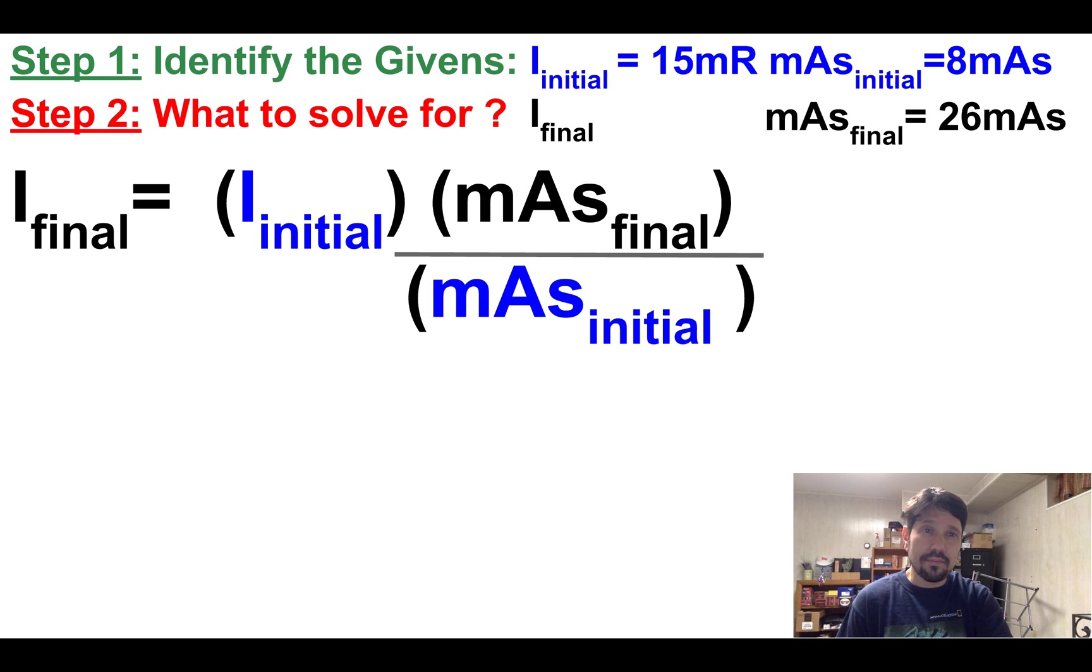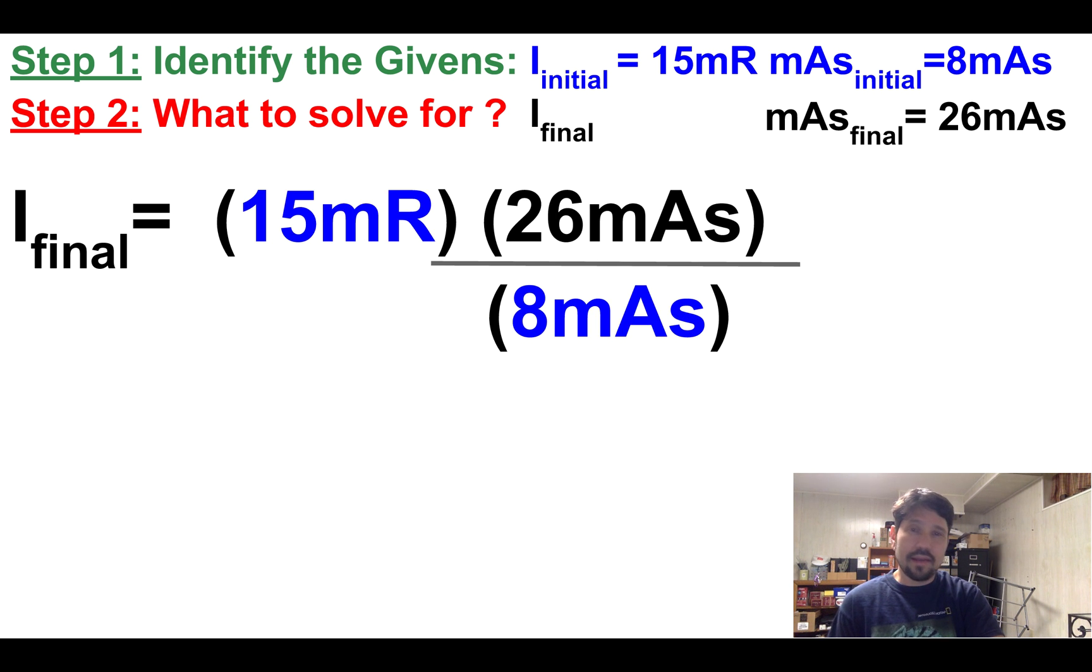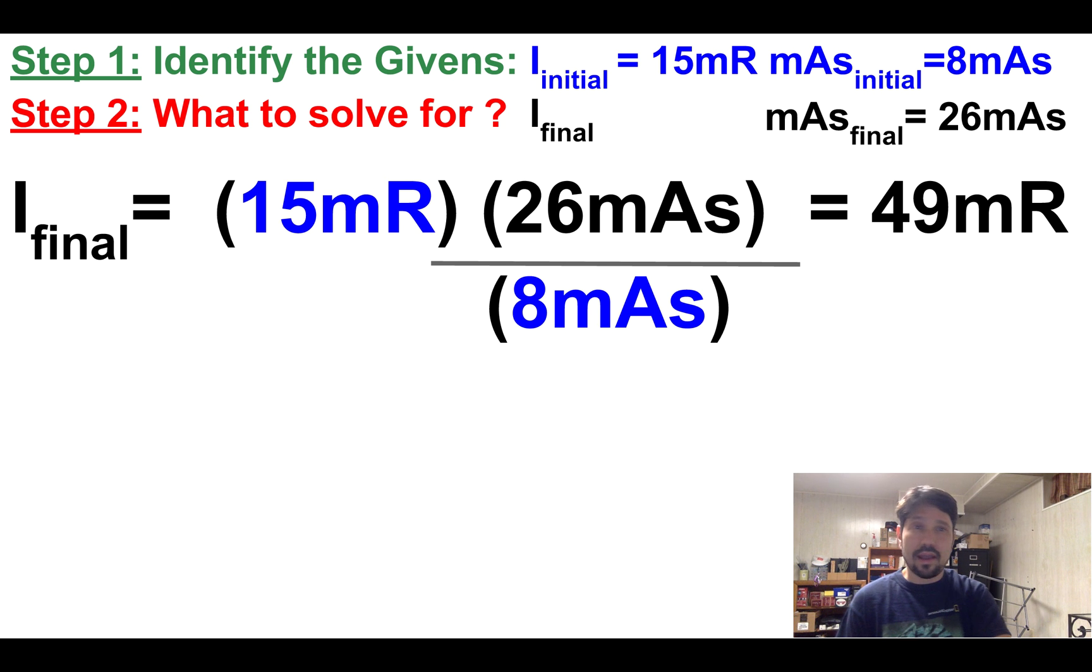So here's my equation, initial times the ratio of masses. And I go ahead and I put in 15 mR initial times the new mAs divided by the old mAs. And that's how I would get 49 mR.